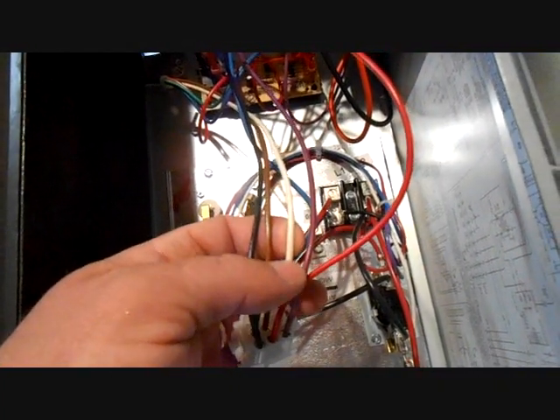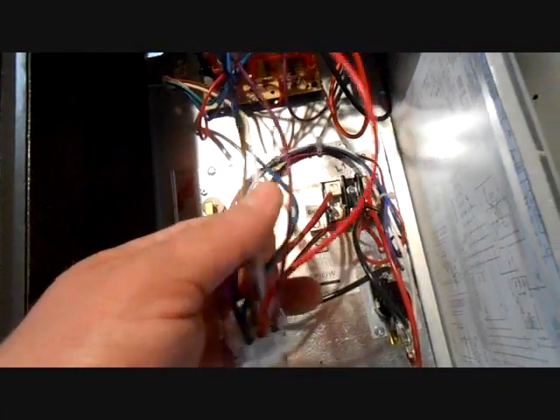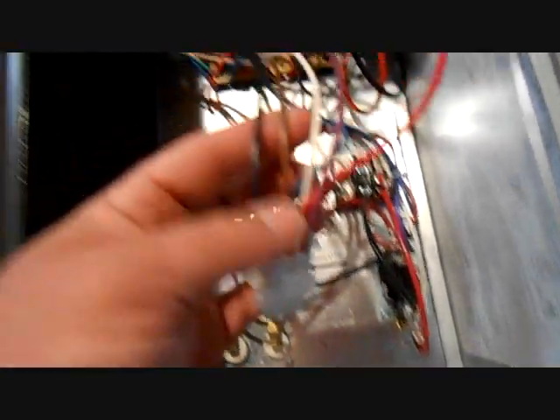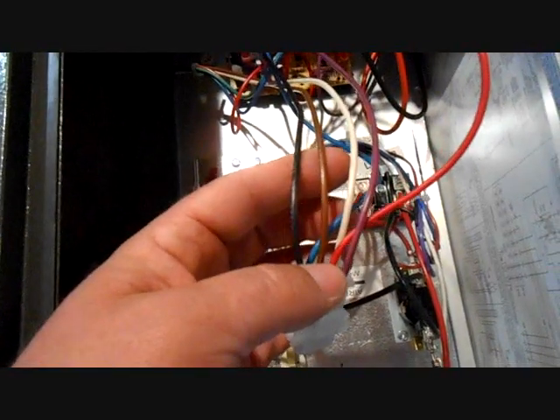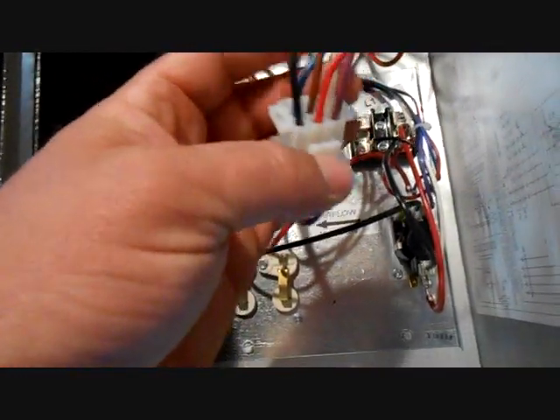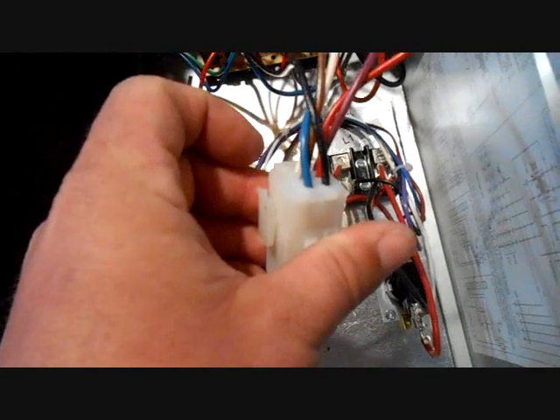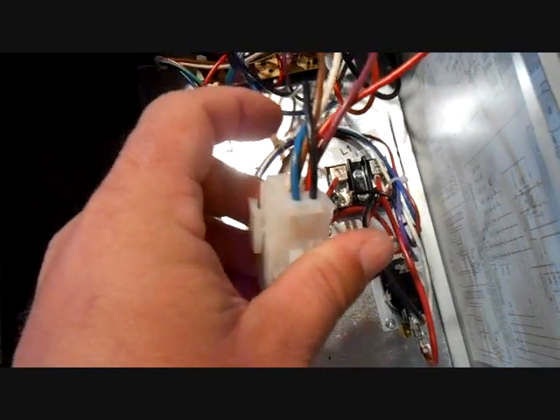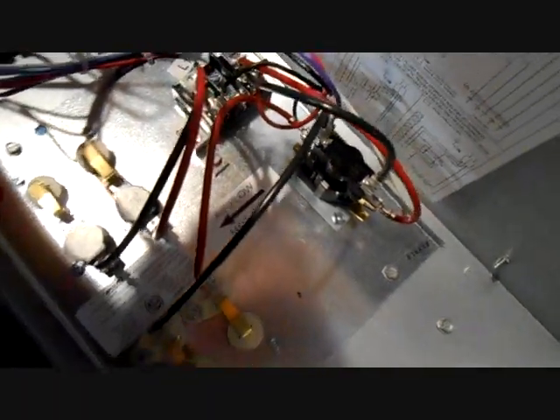White is W2. That will go to the sequencer. Down at the base of it 24 volts. And then you'll have blue. Here's your common. Also going to the sequencer. So it will pull in and turn the heat strips on. And that's about it for the heater.